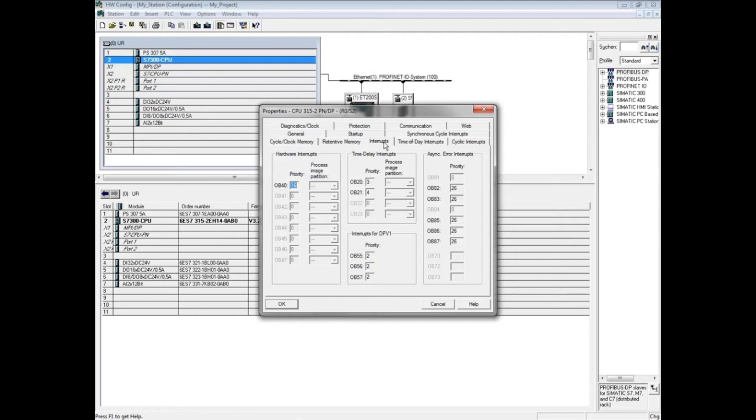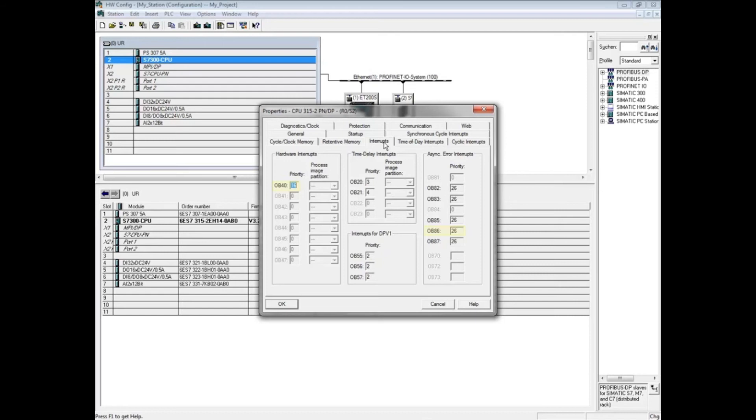For example, if OB 40 with priority 16 has just been launched but there's a Profibus or Profinet network failure, OB 86 with priority 26 would interrupt and execute. While the priority numbers can be changed, it is recommended that you leave them at the default settings.